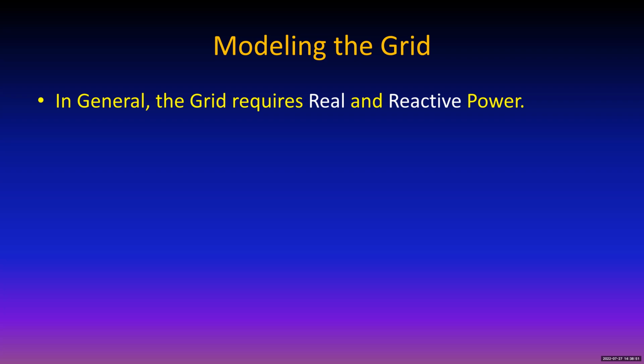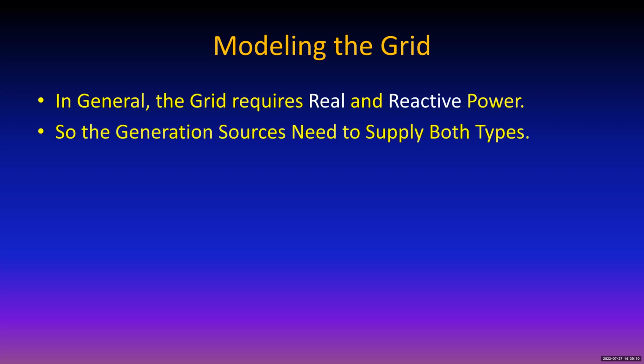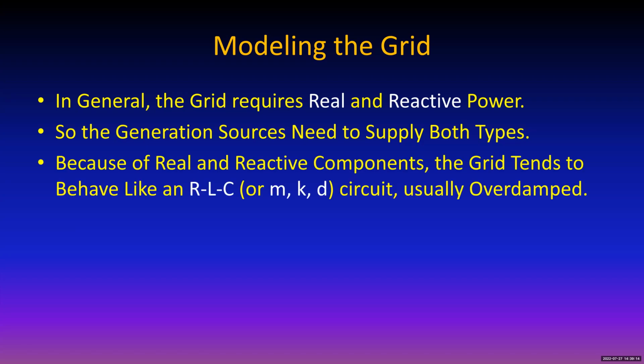And it means that current times voltage would be greater than what you would measure with a watt meter. But the grid needs reactive power, and preferably it needs some reactive power that will offset the reactive power that's being used by the loads. So it's nice if the generation sources can do both.